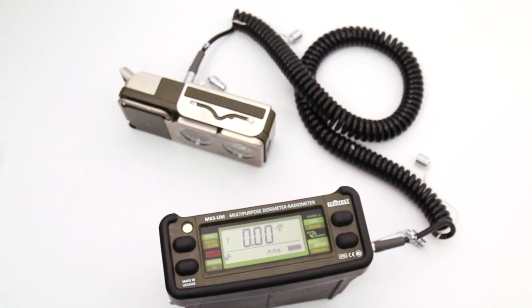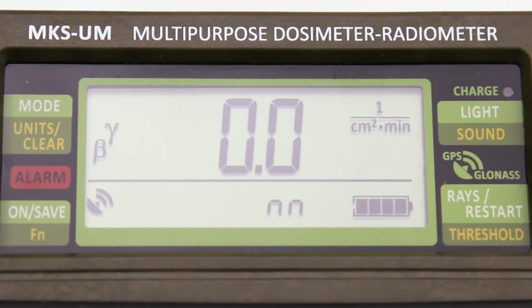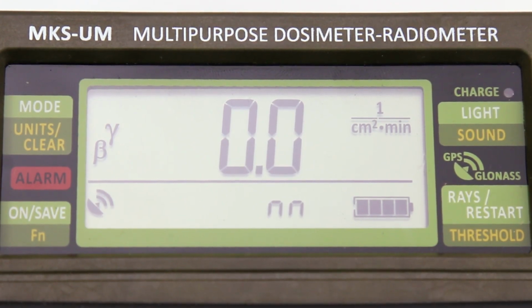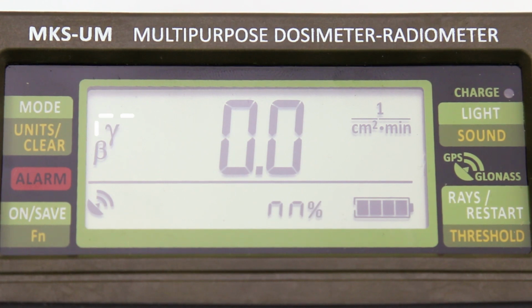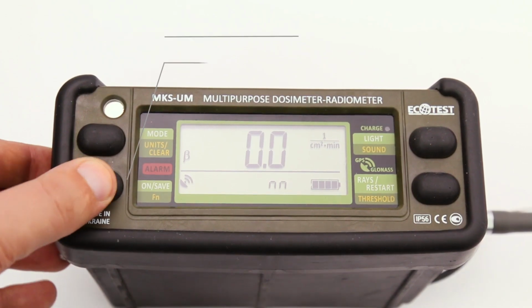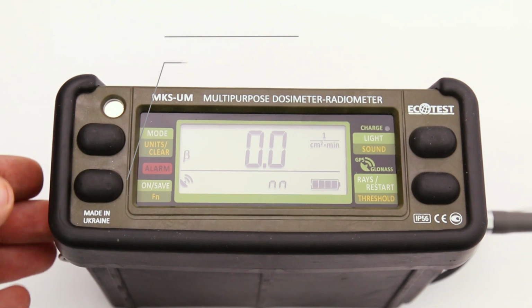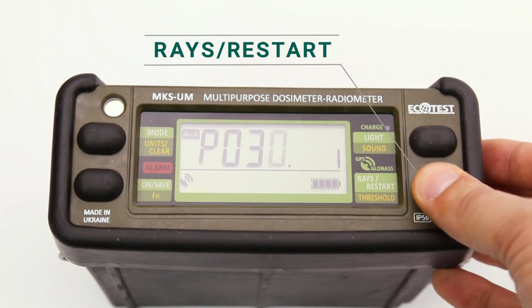You can save the measurement results of the beta radiation only if the gamma radiation is considered. This is confirmed with a flashing gamma symbol. This process is carried out in the same way as saving the result of the dose rate measurement.